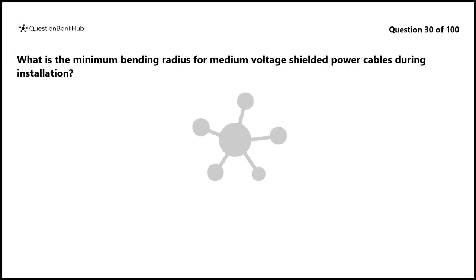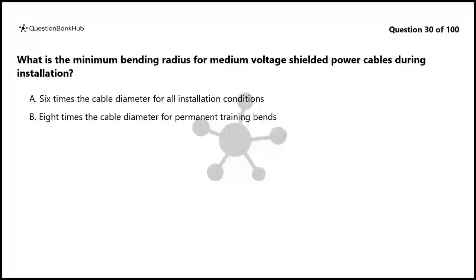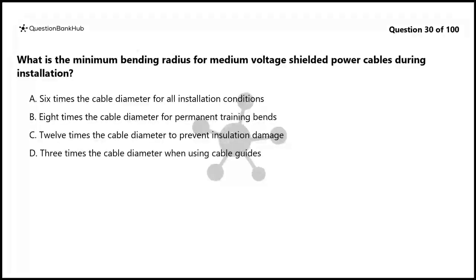Question 30. What is the minimum bending radius for medium-voltage shielded power cables during installation? A. 6 times the cable diameter for all installation conditions. B. 8 times the cable diameter for permanent training bends. C. 12 times the cable diameter to prevent insulation damage. D. 3 times the cable diameter when using cable guides.